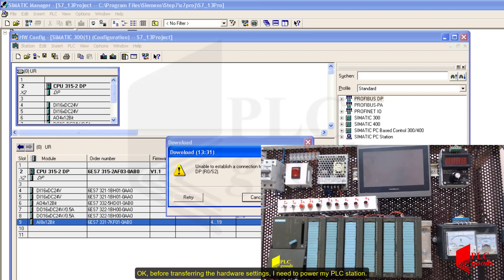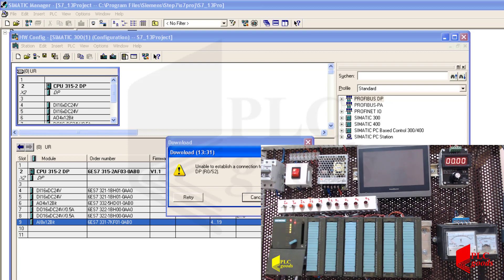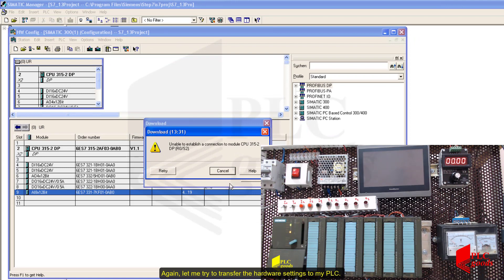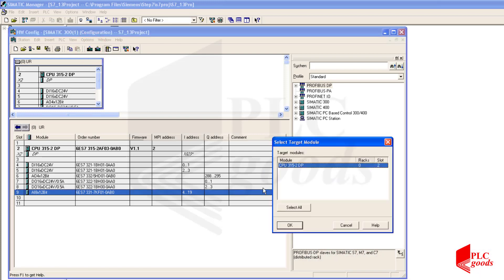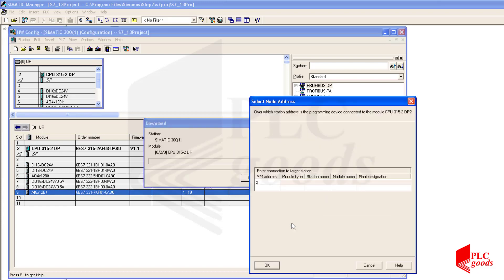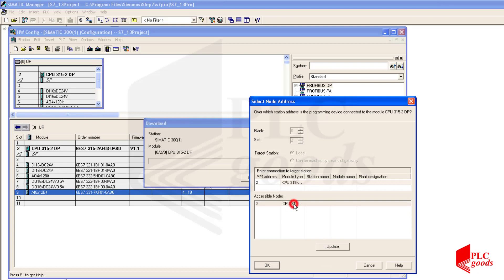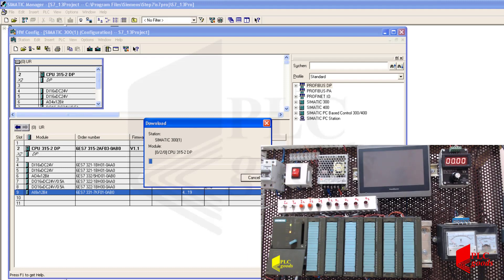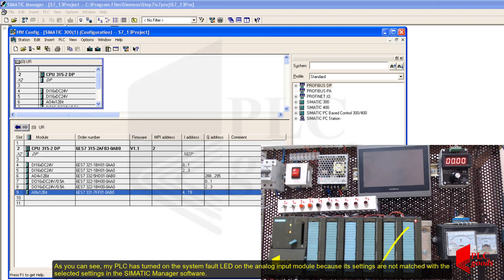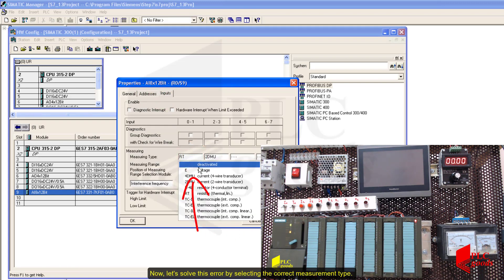Before transferring the hardware settings I need to power my PLC station. Now let me transfer the hardware settings to my PLC. As you can see, my PLC has turned on the system fault LED on the analog input module because its settings do not match the selected settings in the Simatic Manager software. Now let's solve this error by selecting the correct measurement type.